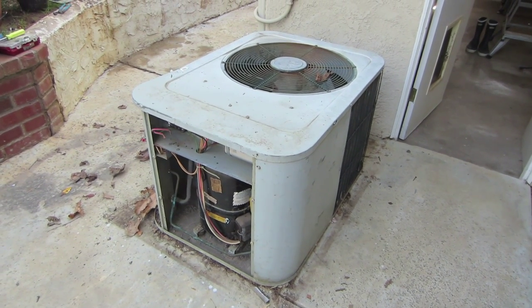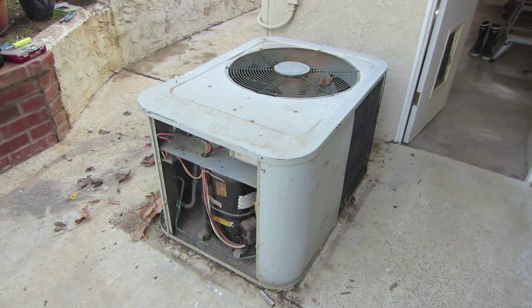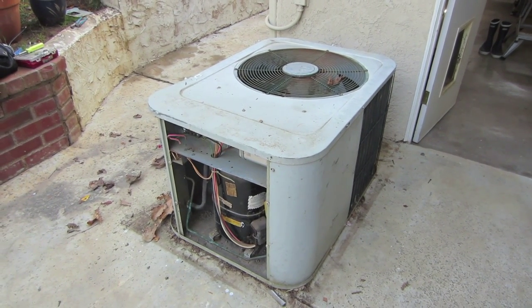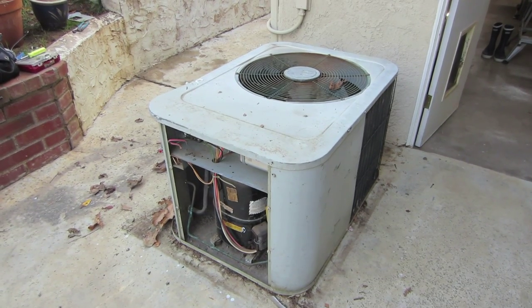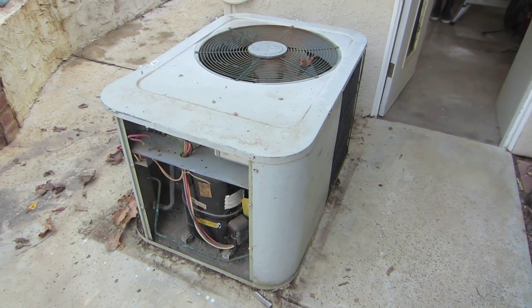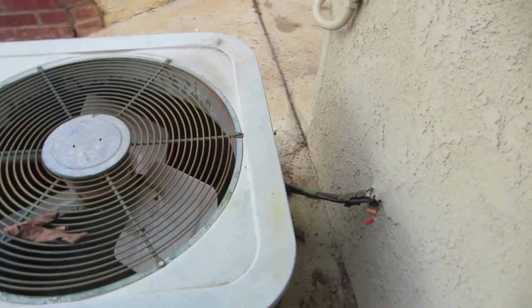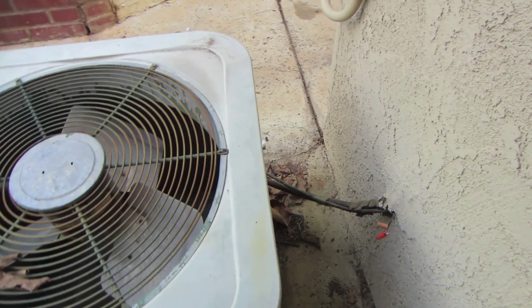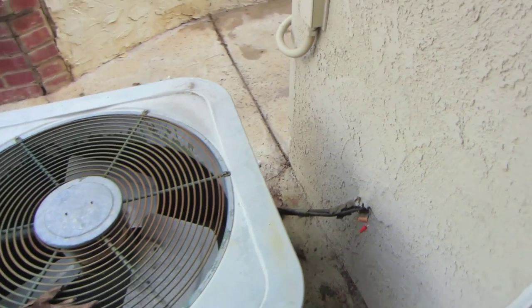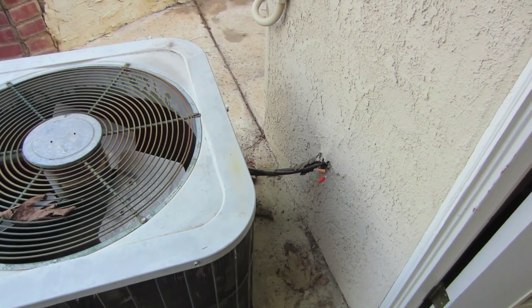Taking this unit out — this is an old BDP 567 5-ton, probably 1981 or 82, it's coming out. I'm going to put a Rheem condenser in there. Tight quarters here, I'm going to turn it and put all the controls on this side because they have animals — their dogs like to chew everything — so I'm going to make it a little bit different. I just took a shroud out from around the unit.